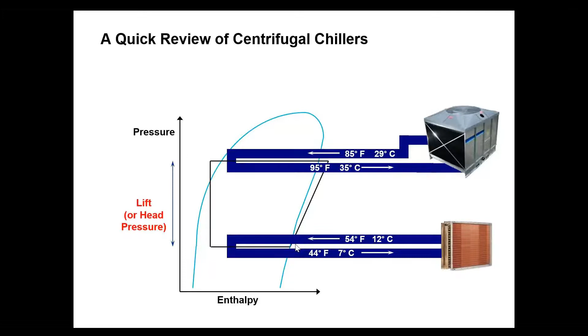So moving on, at this point in time, I'll introduce another important law which the centrifugal compressor follows, because if a phenomenon like this is happening in a centrifugal compressor where kinetic energy is getting converted to pressure energy, then it has to follow certain laws. And those laws, I think we are already familiar with. Those laws are called fan laws. We can probably skip the first two, and I'll just talk about the third one a little bit in depth, because this has a lot of relevance when it comes to the power consumption of the centrifugal chiller and the associated saving that we see in centrifugal chillers. So the centrifugal chiller follows the third fan law, which is that the power is proportional to the speed cube.